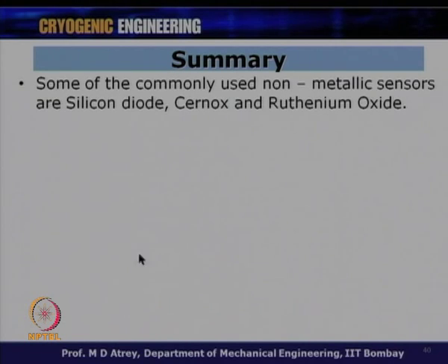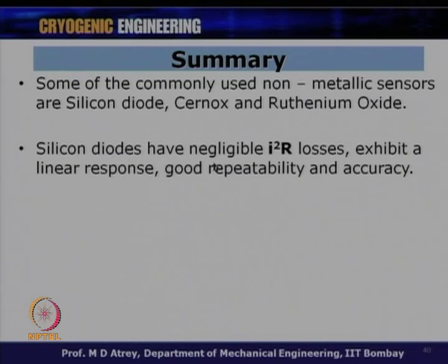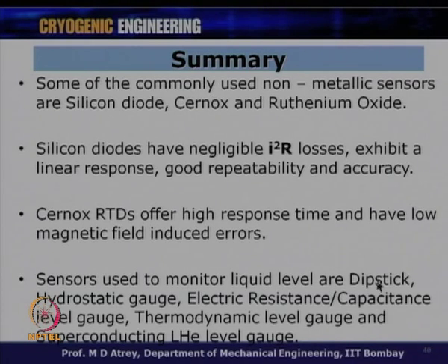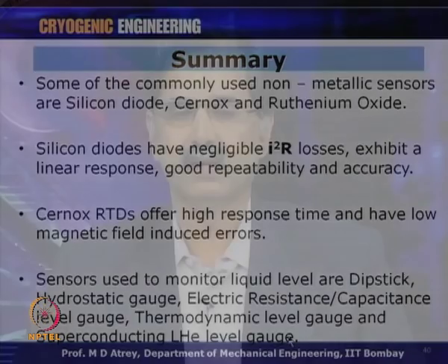In summary: commonly used non-metallic sensors are silicon diode, Cernox, and ruthenium oxide. Silicon diodes have negligible I²R losses, exhibit linear response, good repeatability and accuracy. Cernox RTDs offer high response time and low magnetic-field-induced errors — preferred in magnetic field environments. Liquid level sensors include Dipstick, hydrostatic gauges, electrical resistance or capacitance liquid level gauges, thermodynamic level gauge, and superconducting liquid helium level gauge. Dipstick gives approximate nitrogen level; superconducting gauge is used specifically for liquid helium.